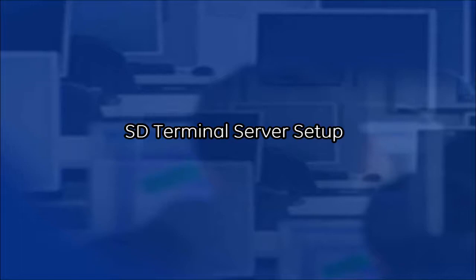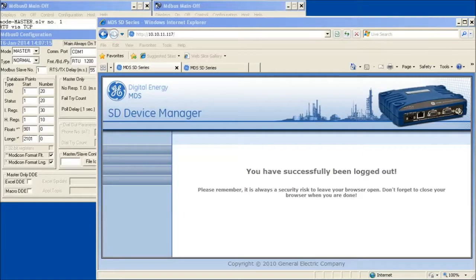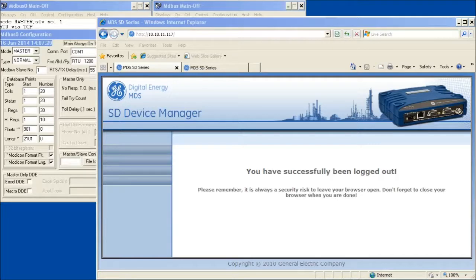SD allows a terminal server to be enabled on both COM1 and COM2. When terminal server is enabled on a remote, the access point can send IP messages to the remote via its IP address. The remote will receive the IP message and encapsulate it into a serial message that will pass through the enabled serial port connected to the RTU or PLC device.